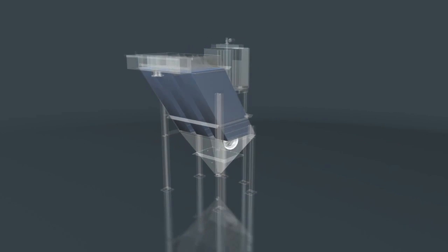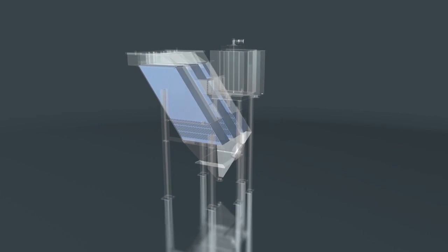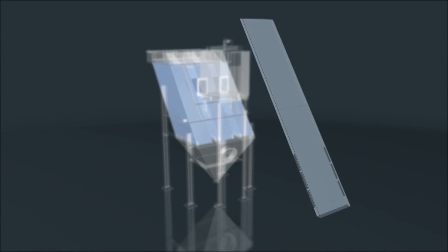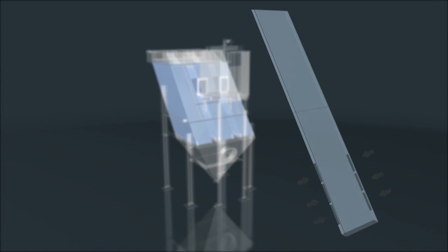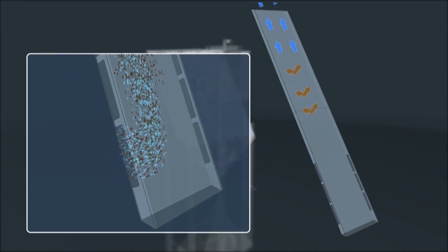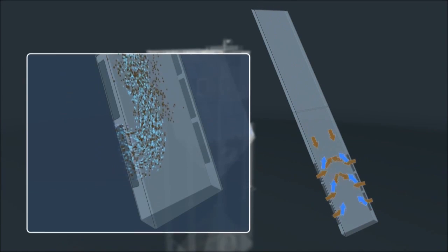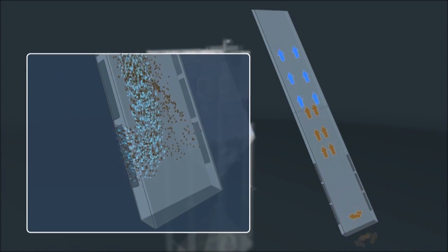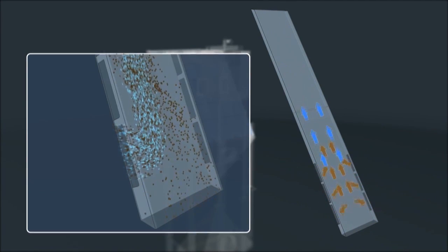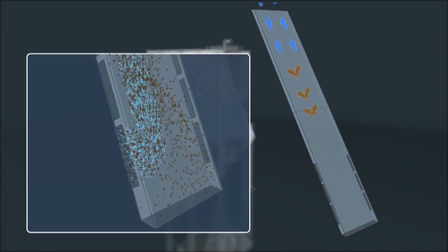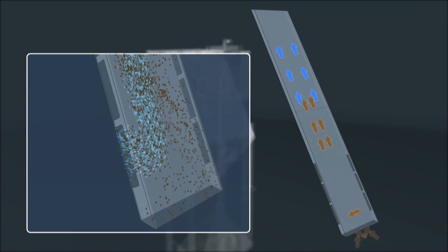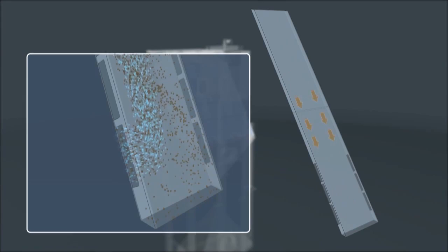The most significant aspect of a gravity settler's design is its available settling area. The effective gravity settling area of the inclined plate design equals each plate's area projected on a horizontal surface. The original Lamella could only use 80% of the total plate surface area. This is because the path of the influent flow collided with the solids moving down the plate, causing a zone of turbulence that cannot be used for settling. This 80-20 split is the current industry standard when sizing a plate settler. To overcome this phenomenon and achieve 100% use of the plate area, the flow at the feed slots needs to be redirected away from the solid settling path.